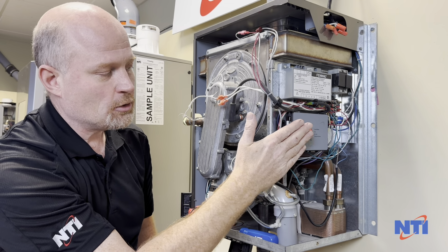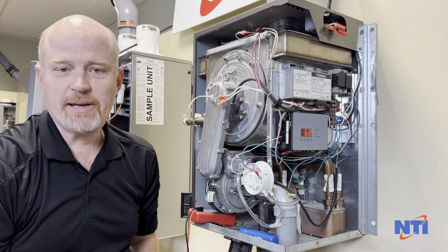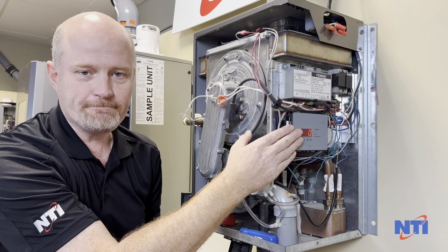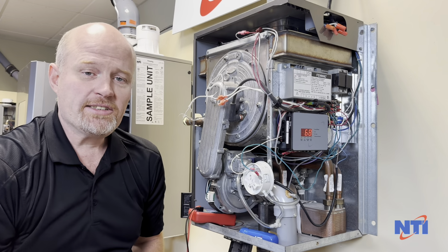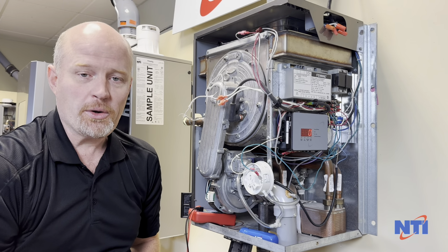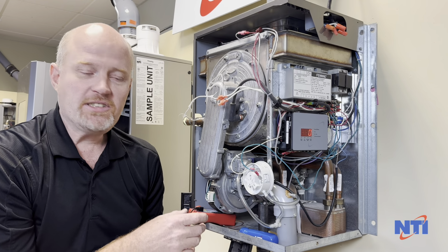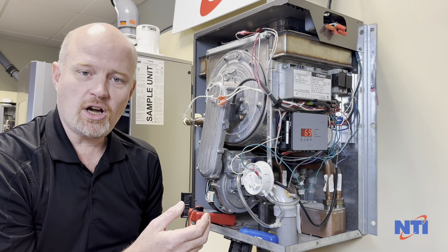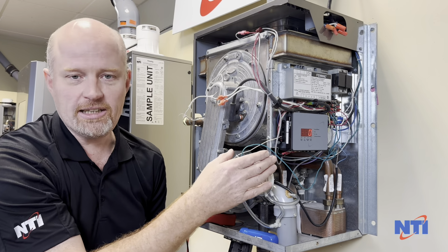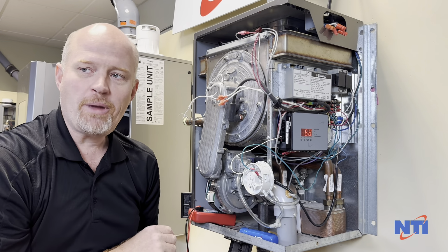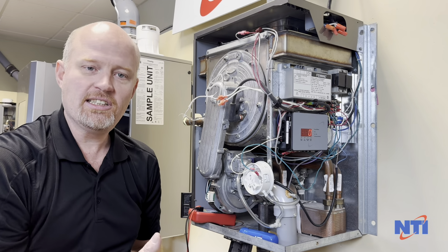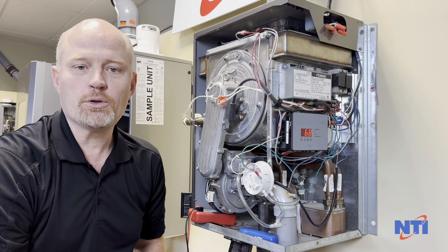If you've checked all that though, and you still get the problem, it is a bad Sentry control and you'll want to replace that. This also applies to error code T4.1 on the TI 400 boilers. T4.1, again, it's the version of the software, but if it's blinking repeatedly, it usually means the control memory's gone bad and it's just rebooting continuously and you need a new controller.